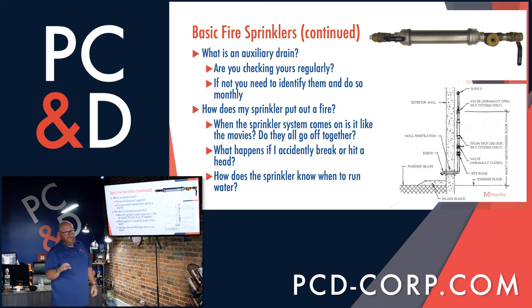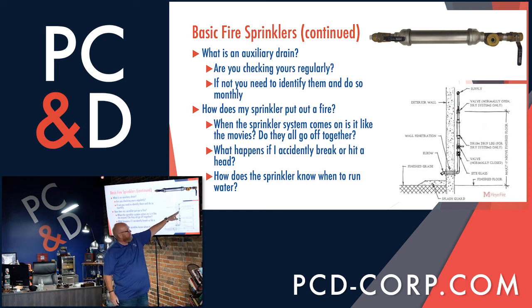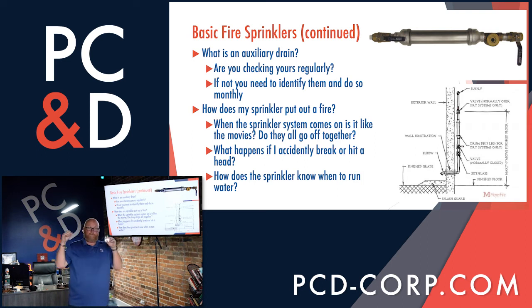One of the worst things that we can do is not know where our low point drains are. And you may say, why, Mitch, what's it matter? If this continually is building up with water, that water can and will eventually back its way up all the way into your attic because it's never been drained and it's your low point. All of your water is going toward it, but if you're not draining it in a timely manner, that water is going to build back up into the attic, okay? Cold water in an attic and it's 10 degrees in the attic, what happens? It freezes. Water lines freeze. When they go to thaw, what happens? They bust. That's why we have to continually check and drain our low point valves.